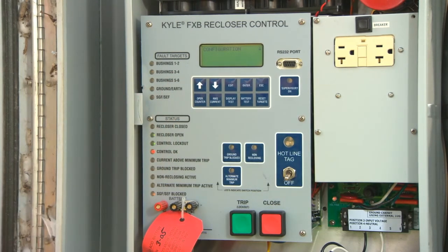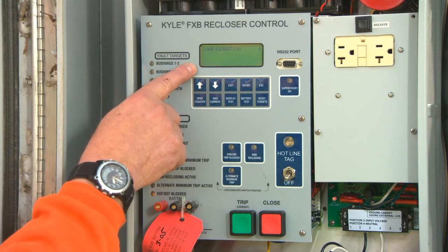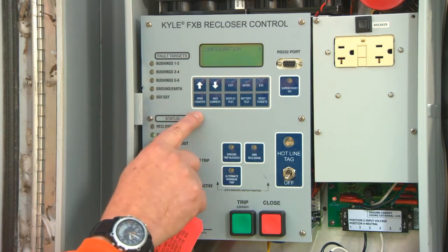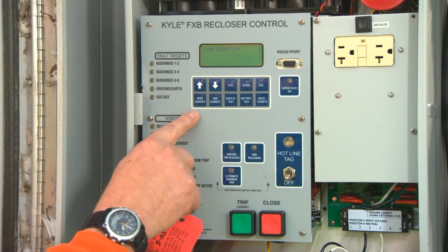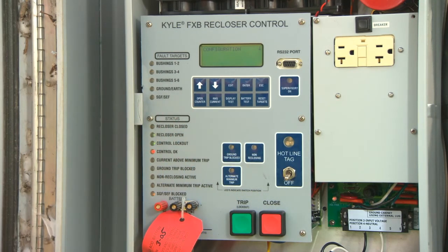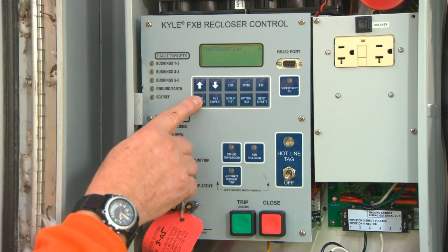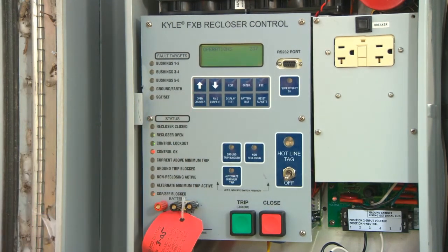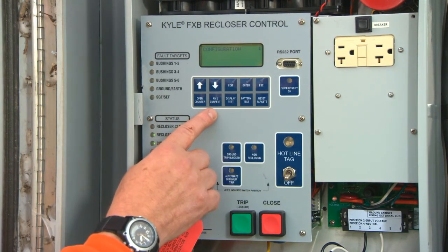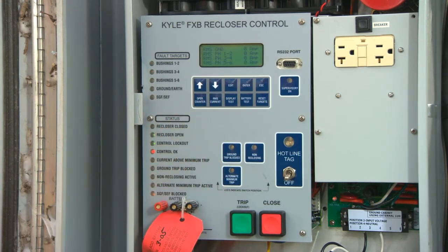When you open the enclosure, you will see the word Configuration on the green display screen. The selection buttons across the bottom will allow you to access the system and perform various control checks. After selecting Counter Operations, you will notice the screen displays that this particular unit has gone through 237 operations. Pressing Escape will return to the main menu screen. Pressing RMS Current will display the current that is flowing through the recloser.